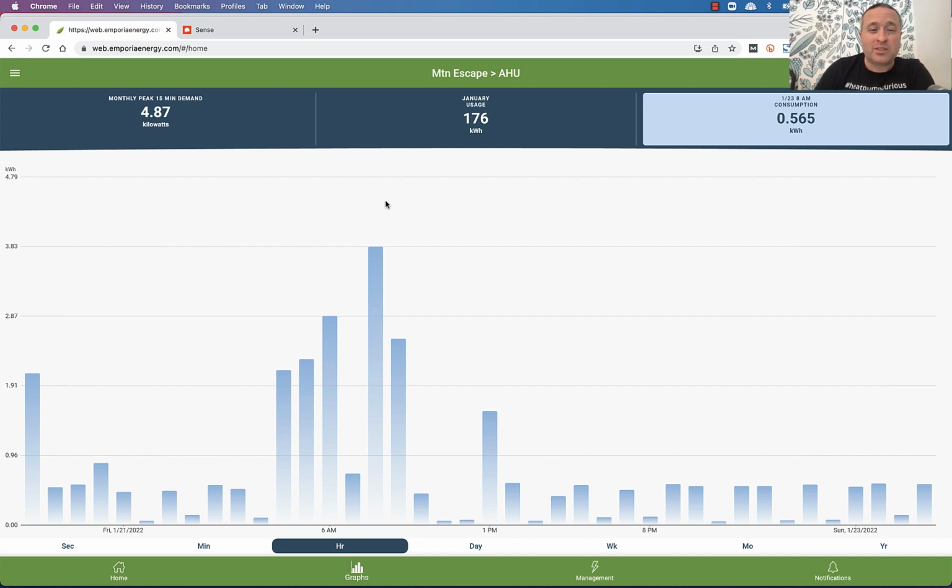So I have the heat pump set to 2 tons, but it has a 3-ton load at design. As this was happening, it was about 10 degrees outside, which is our design temperature here, which means we only spend 1% of the year, or 88 hours a year, below that temperature. That's what you're seeing here. And I thought this was pretty cool. All of this usage right here works out to 14 kilowatt hours total. So I have a 3-ton load house that only has 2 tons of capacity, and to make up that difference for a cold morning was 14 kilowatt hours.